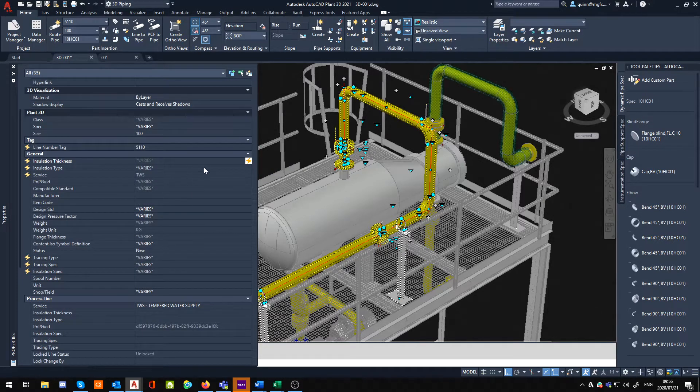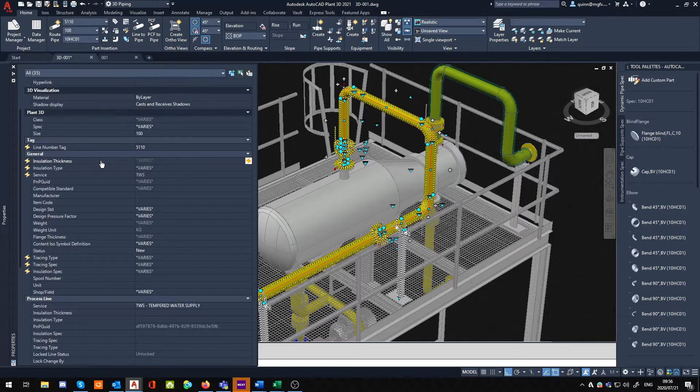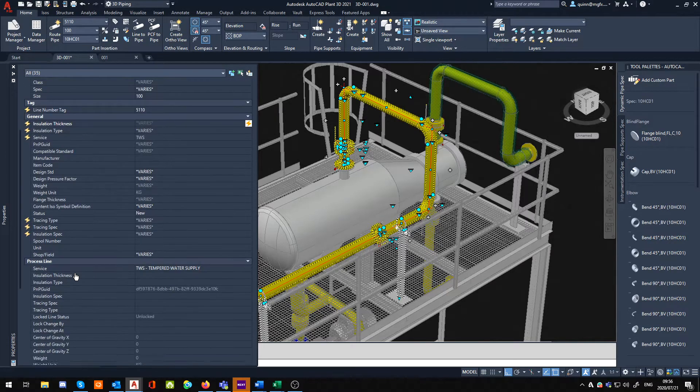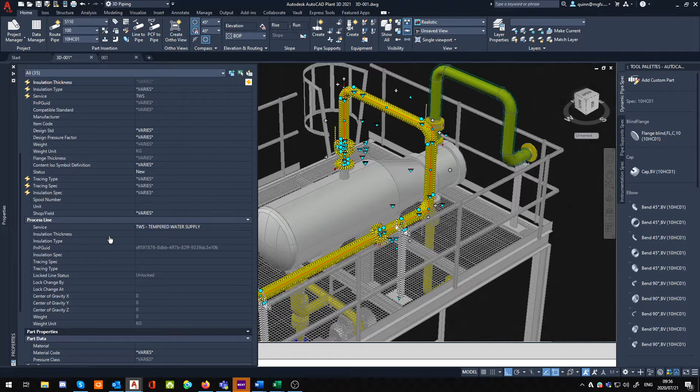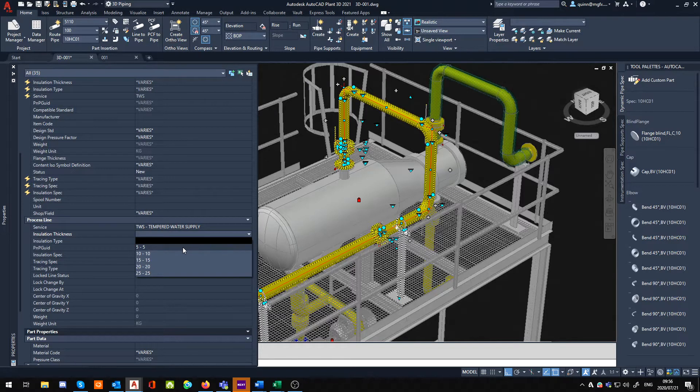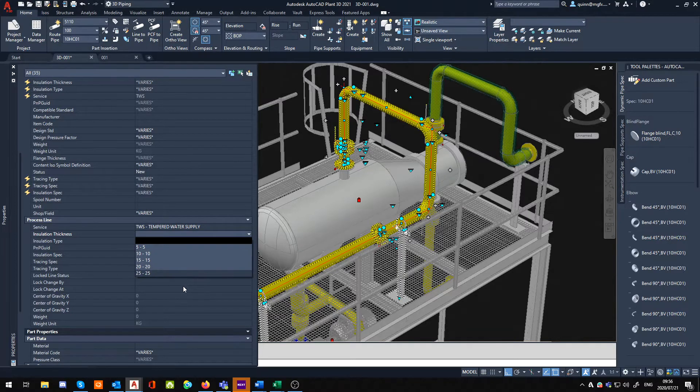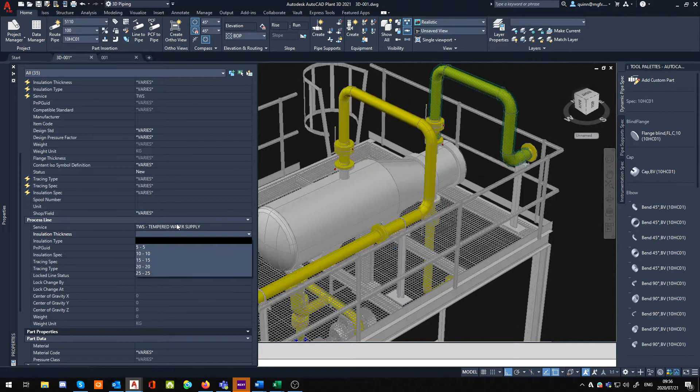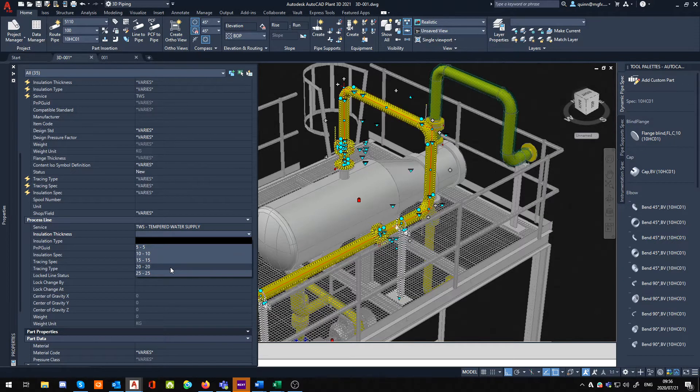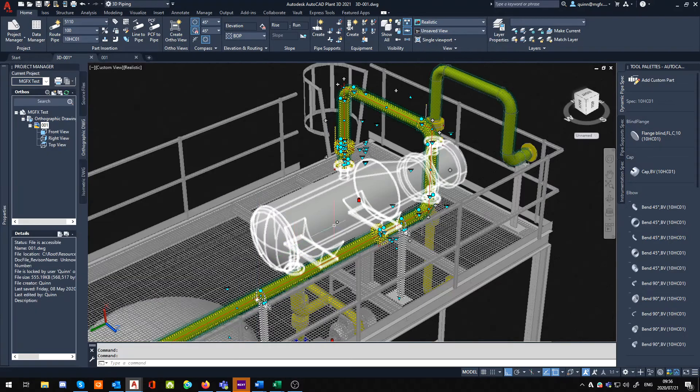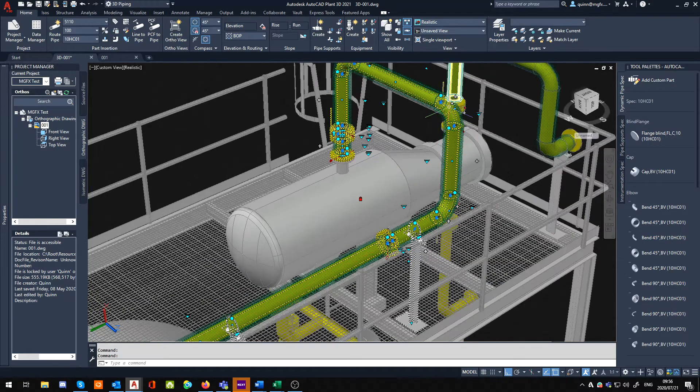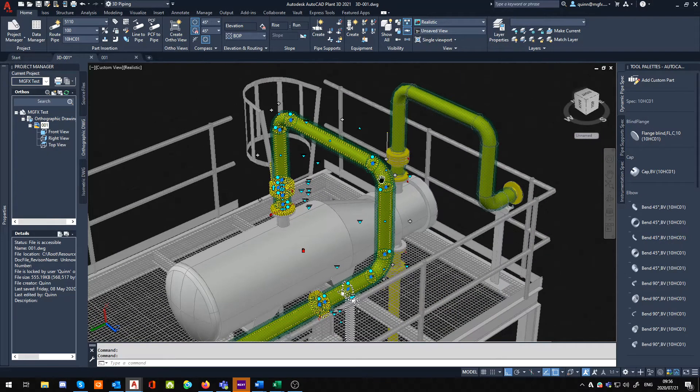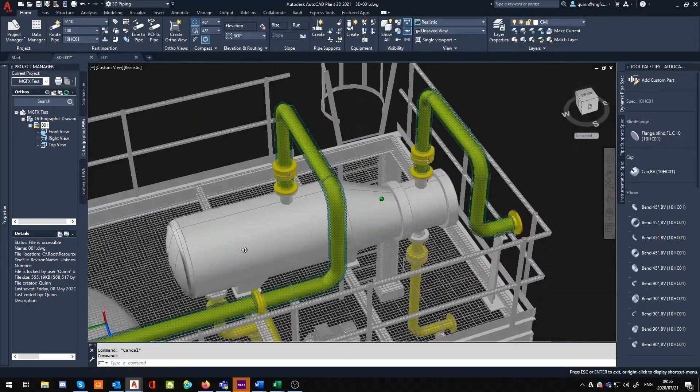All you have to do is just scroll down a little bit because it's not here in the general, it's actually down here in the process line. In here you can use the dropdown and then select, by default, these 5, 10, 15, 20, and 25 millimeter thickness. So I'm going to say, okay, let's make this a 25 millimeter. I'm going to select it. As you can see, if I escape to go off it, we have now assigned our insulation.